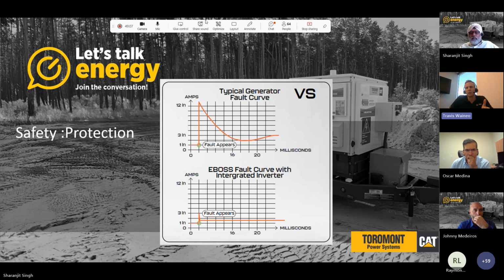For example, a normal arc flash protection boundary on a standard generator might be maybe 90 centimeters or close. It's actually closer to, I think, a meter plus for arc flash protection on a standard generator. When we did the arc flash protection calculation on this system with the inverter driving the output, that arc flash protection boundary was like 71 millimeters, which means that on this 70 kVA system the arc flash incident energy is significantly reduced.